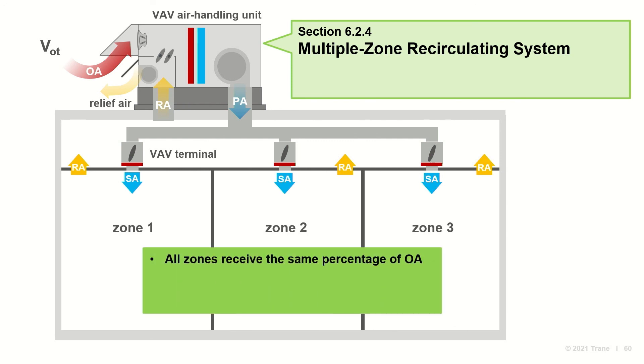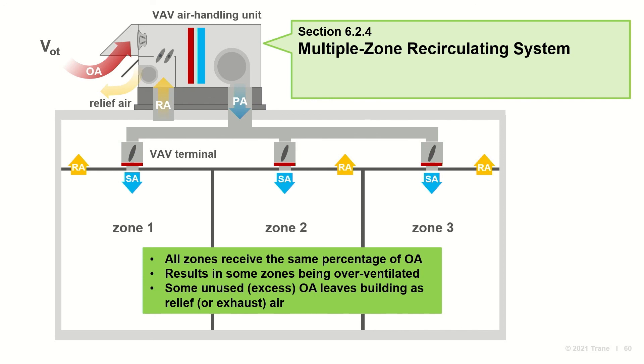Every zone receives the same fraction of outdoor air. As a result, when the critical zone — the zone requiring the highest percentage of outdoor air — is properly ventilated, the other zones will be overventilated. The air returning from these non-critical zones contains some unused or excess outdoor air. Most of this recirculates, and Standard 62 gives credit for it. But some leaves the building as exhaust or relief air without using its full diluting potential.